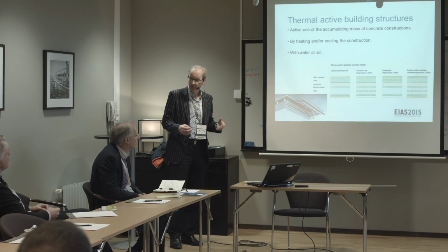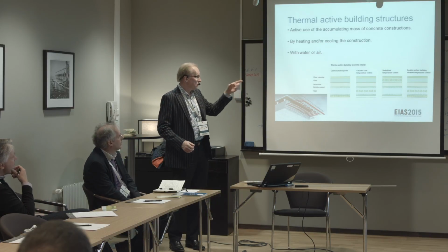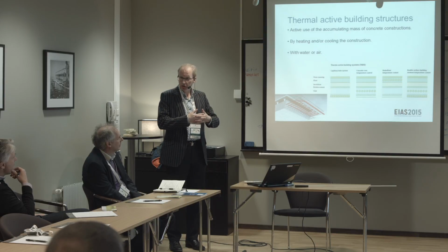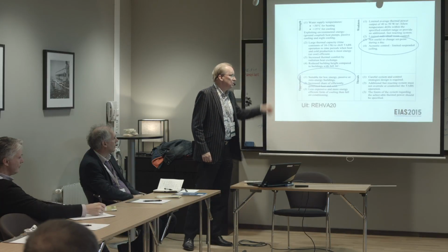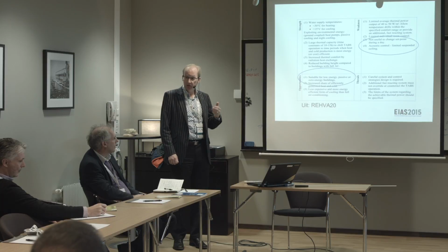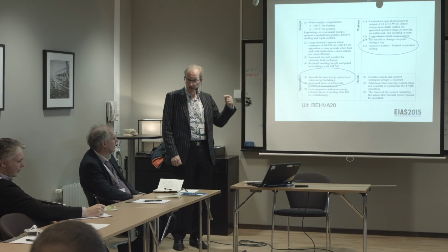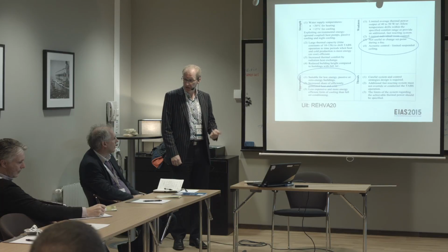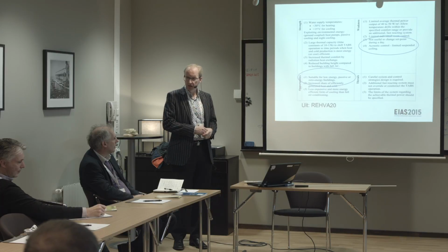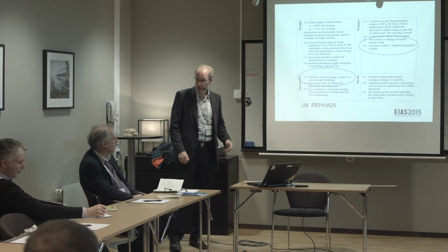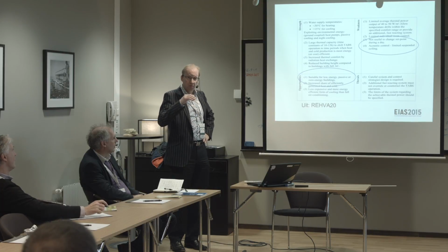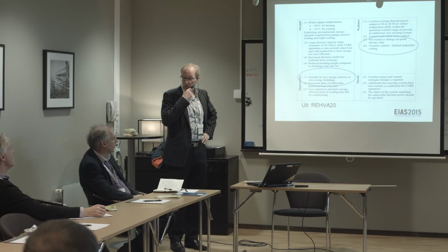What are TABS? For me, TABS are slabs in which the temperature is changed by water or by air. And the main opportunity of that system is low energy, passive or zero energy buildings. When we really want to achieve zero energy buildings, we have to go down in the amount of energy for heating and especially for cooling. We have to go down in temperature, bring them near each other to exchange with water or with geothermal sources. And then TABS gives you the best comfort for the lowest costs.